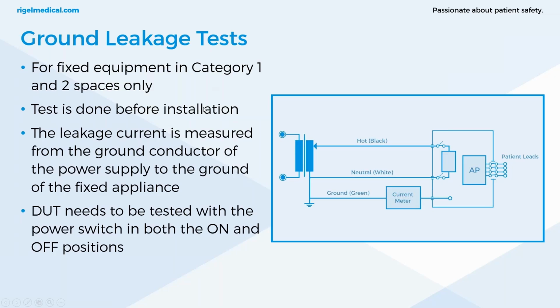So the leakage current is measured from the ground conductor of the power supply to the ground of the fixed appliance, and the current limit for this test is 10 milliamps, and the power is switched in both the on and off positions. So you're carrying out 2 tests.